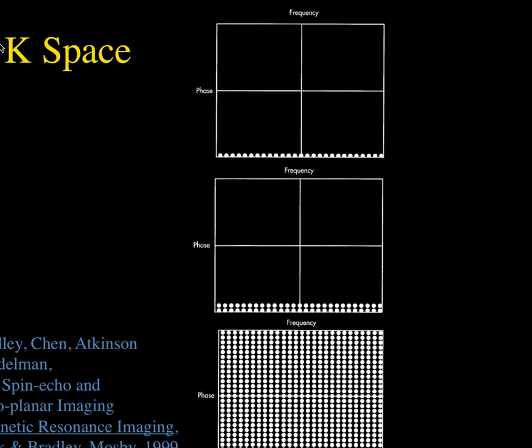So K-space is really a three-dimensional array of signal intensities from what we've received from the electrical impulse that comes in the wire from the person's body. It comes in as an analog signal. We digitize that, and then by using the different gradients, we're able to take the segments of energy associated with the different voxels and store that in that signal intensity. That's how we fill K-space.